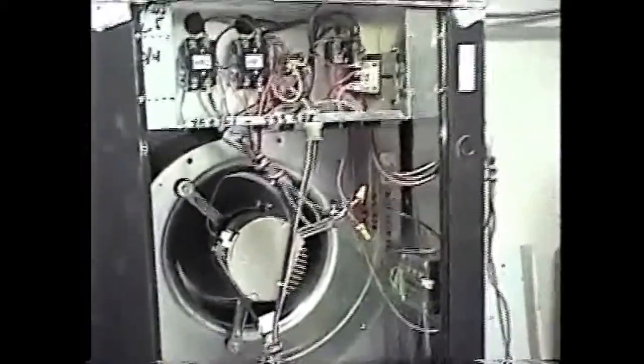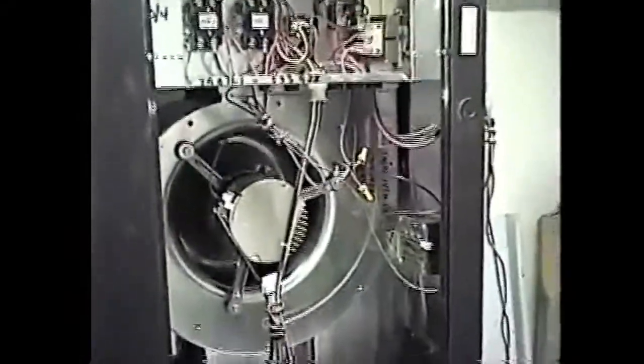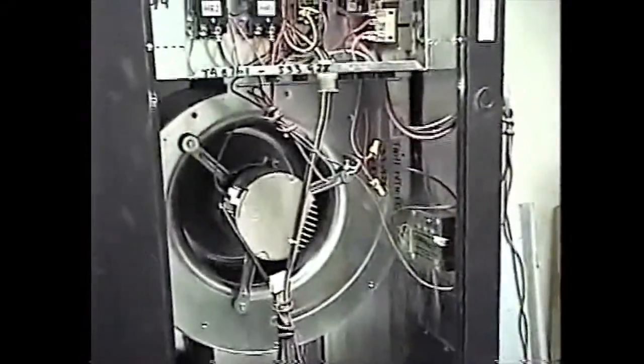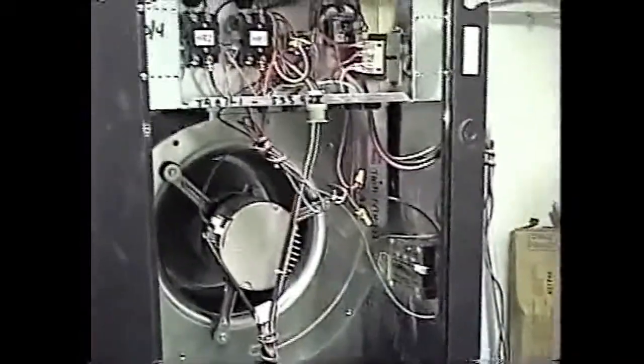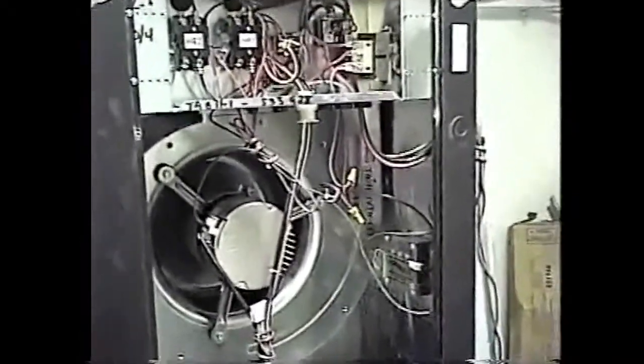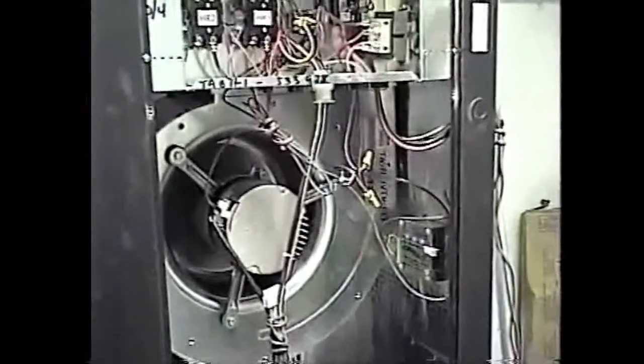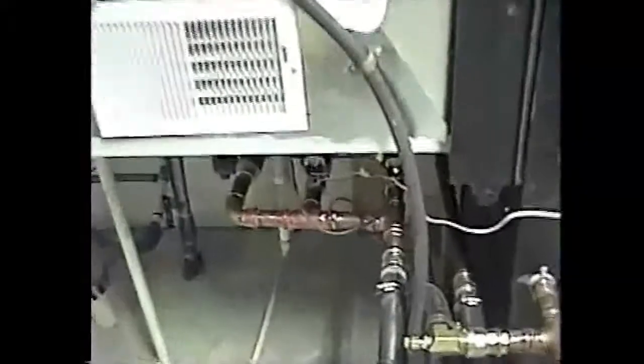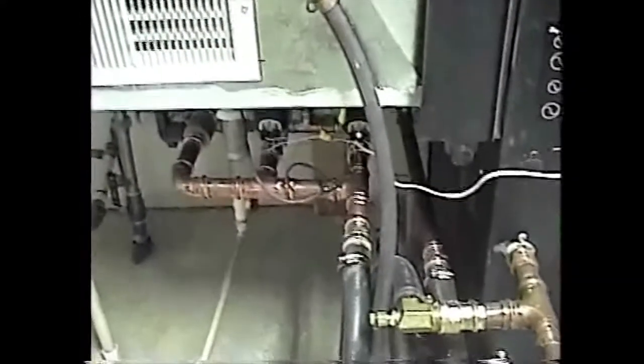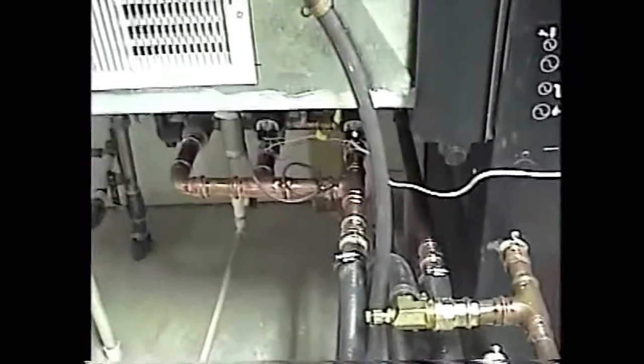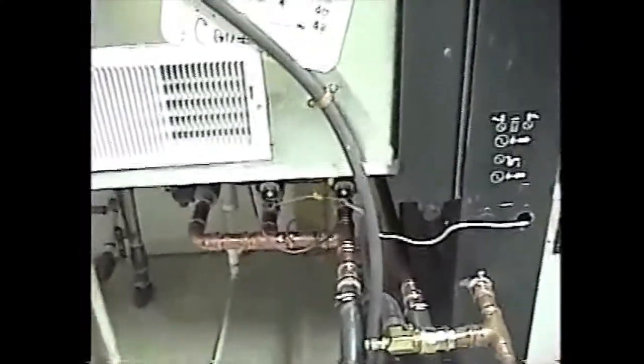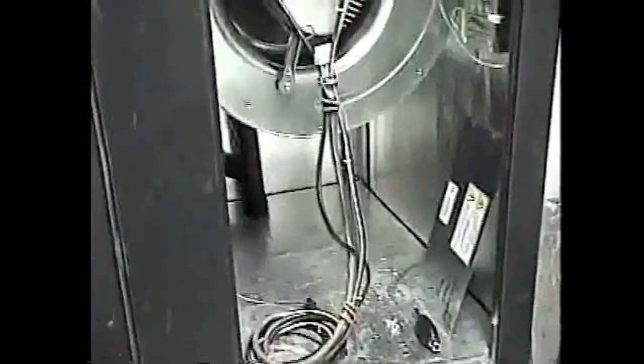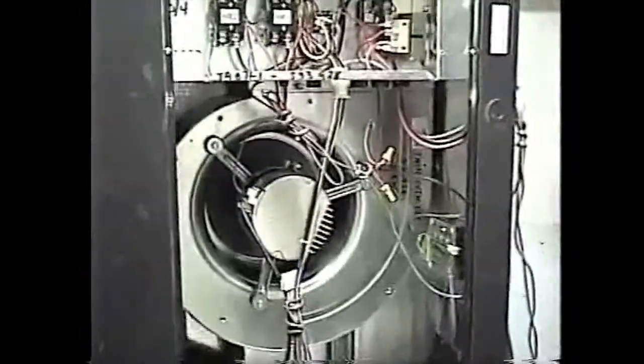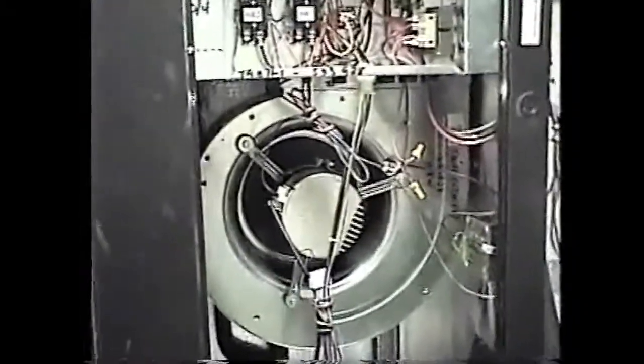So I don't need to have monitoring hooked up so it can call me day or night. I don't need to use my smartphone to tell it what to do. I already used my smarts and told it what I wanted it to do. I checked it, it did it, I walked away from it. It looks like now it's called for a second stage. So when it actually starts, it's going to ramp up on the high-speed compressor, and we're going to see a pretty good spike in the way the fan motor ramps up.